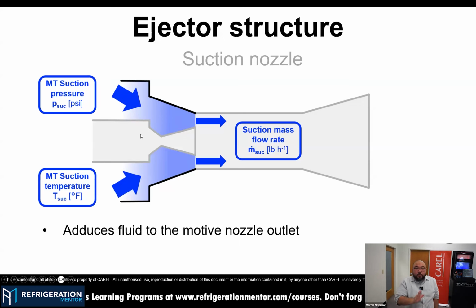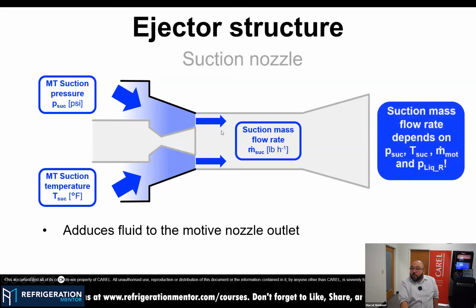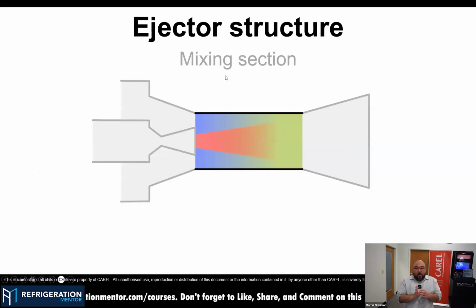conditions so that the refrigerant flow will prefer to come in this direction, okay? And at this point, we have a mixing area. I have high refrigerant flow with high speed and high pressure, reducing the pressure, and I have this refrigerant coming from the medium temperature, low speed, and increasing the speed. Here we come to an average pressure that normally is the liquid receiver pressure from this combination. So I'm basically mixing the refrigerant that comes from the gas cooler and the refrigerant that comes from the suction port.